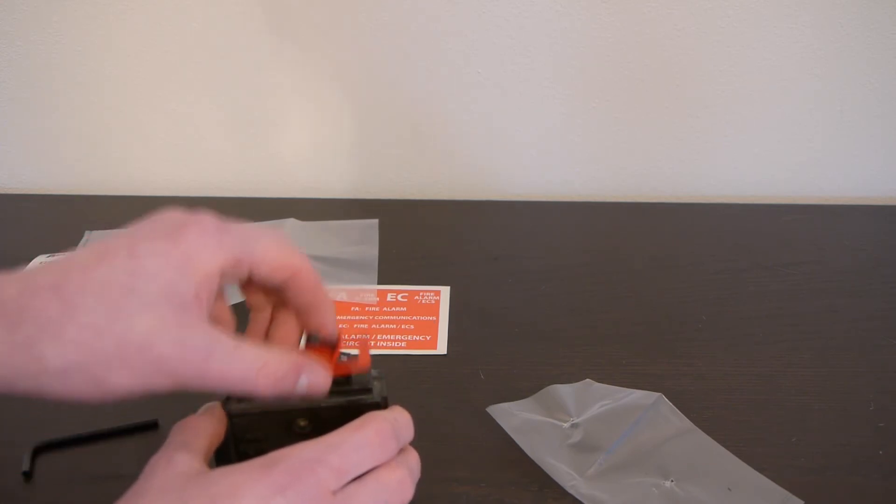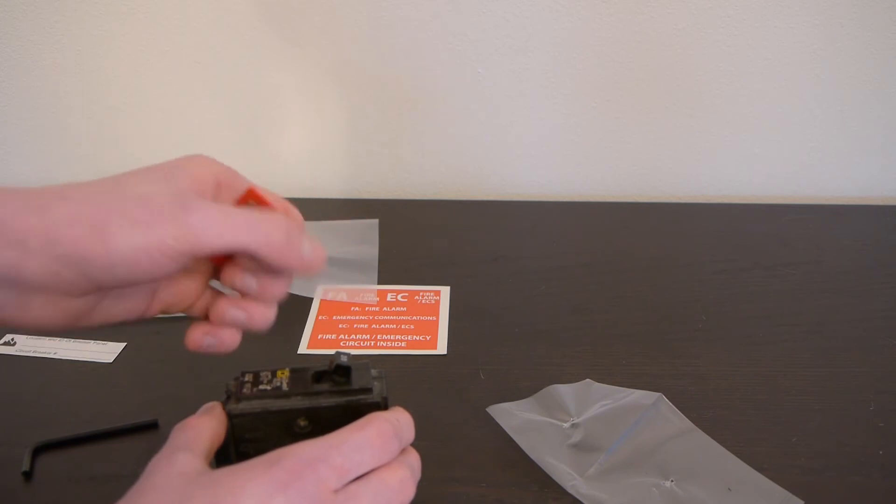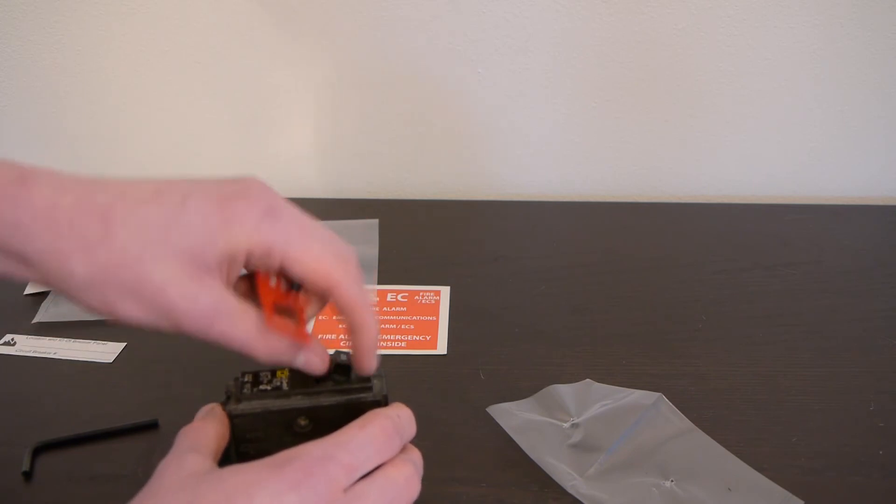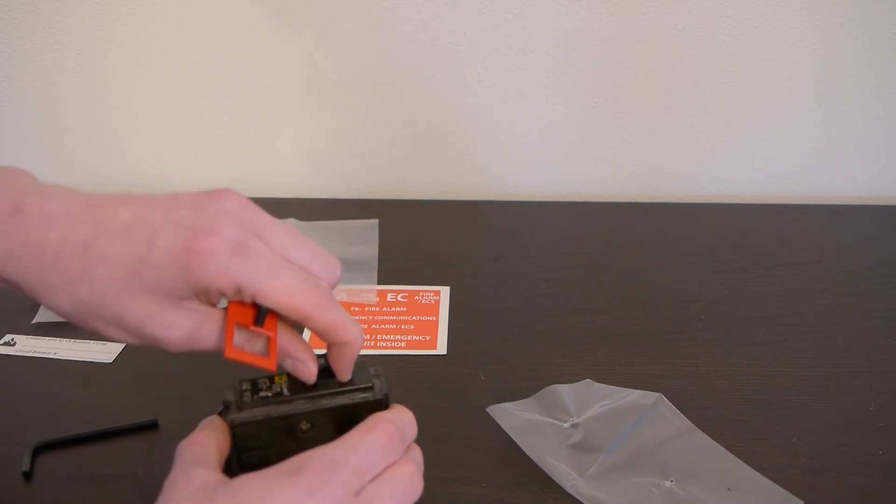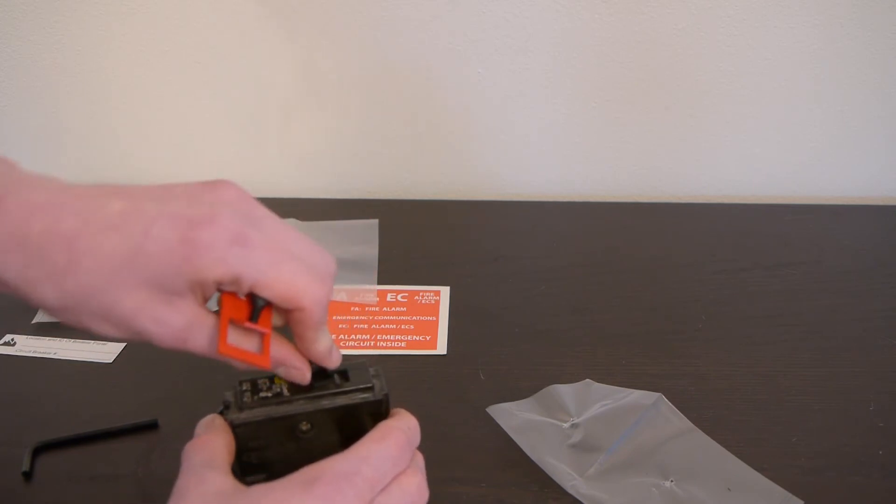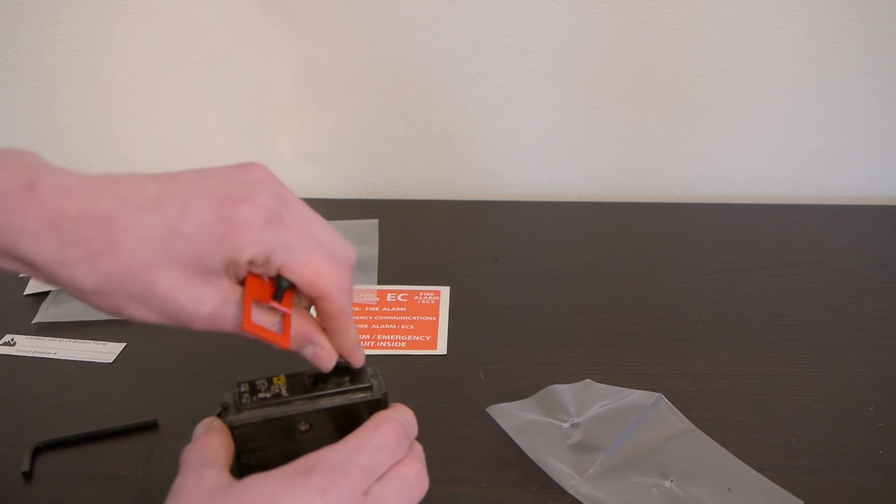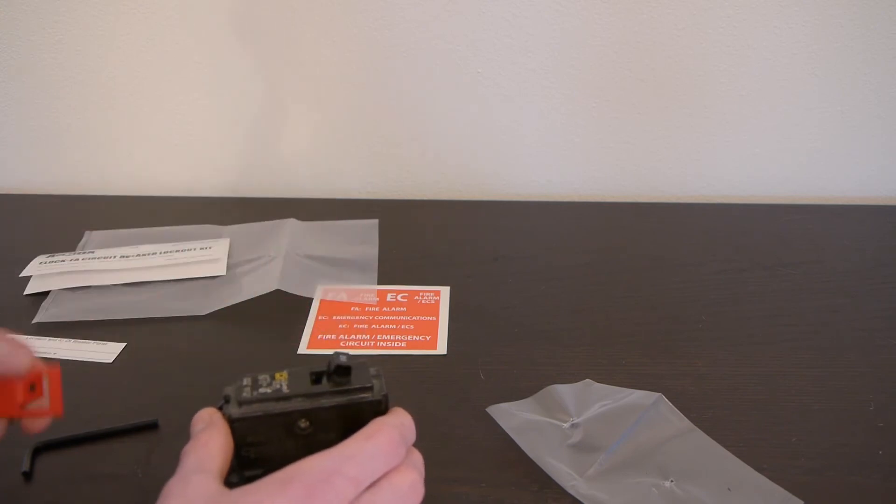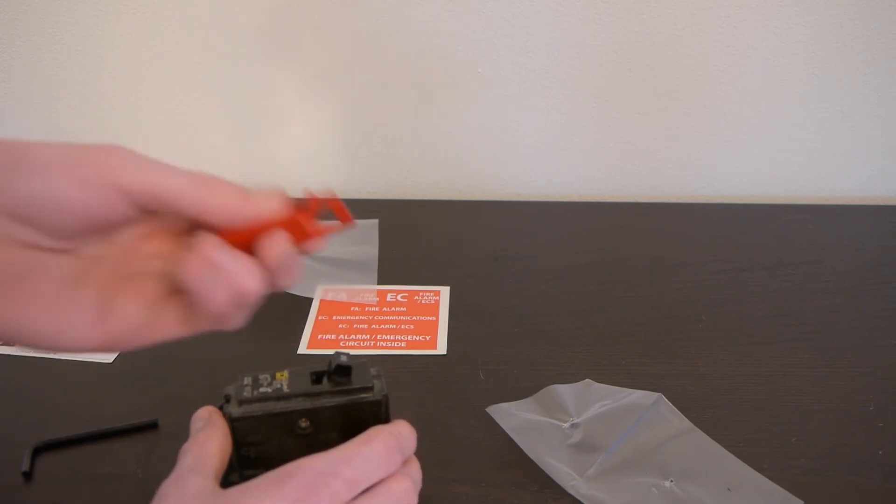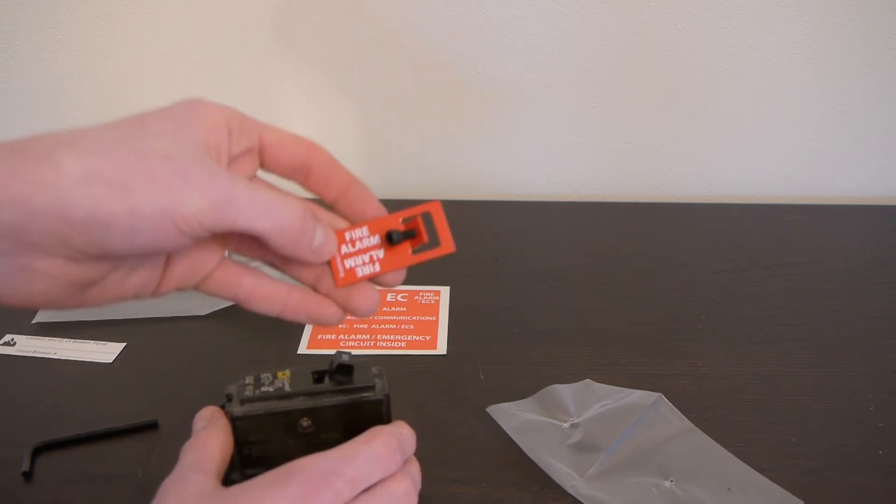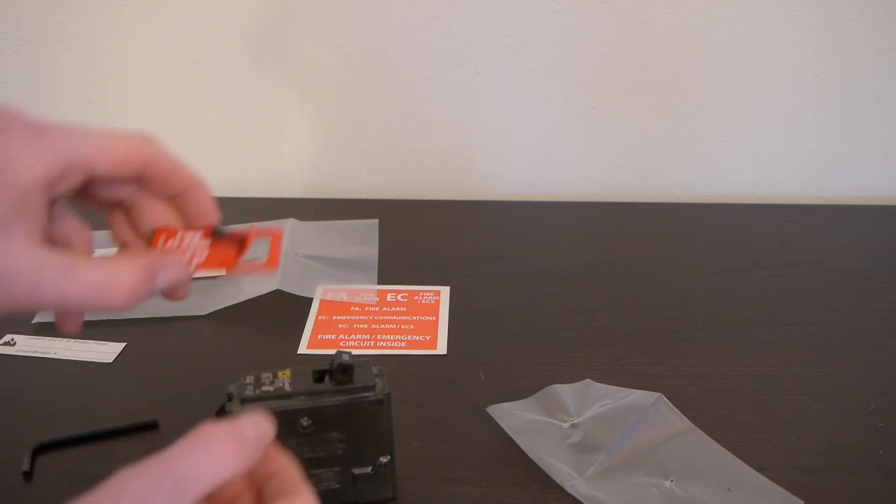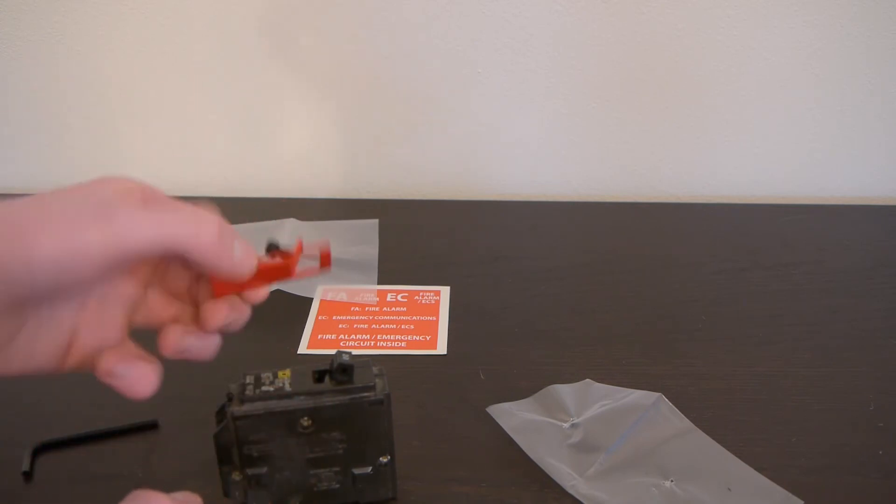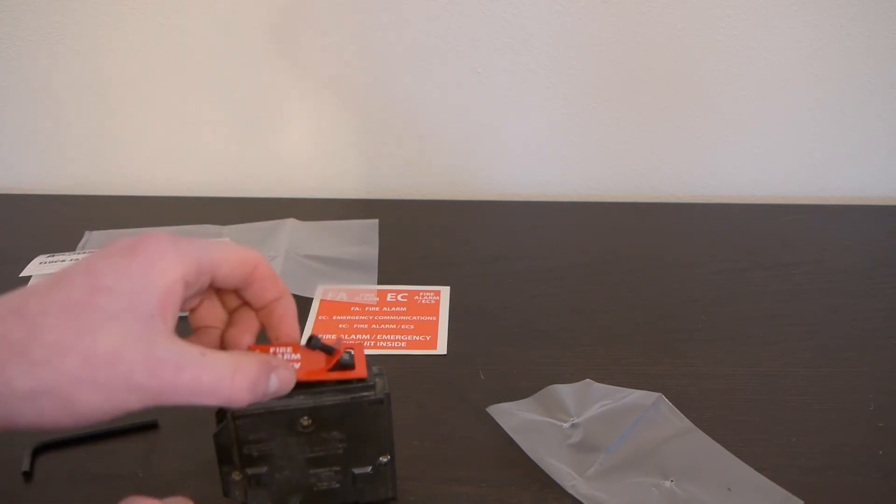So if it were to trip, you'd just take this off, and then this breaker would go down to the middle position, and then you'd have to flip it off and then back on again. So no, this does not prevent the breaker from tripping. It just prevents people from accidentally turning it off.